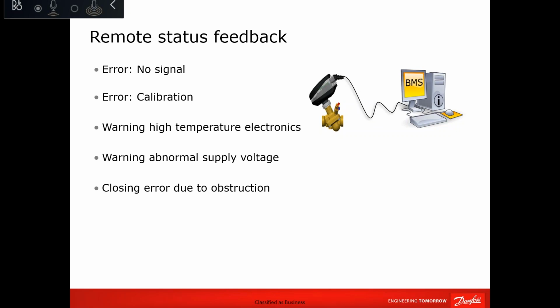Also, if the actuator is closing the valve and something is stuck inside the valve, anything can be stuck inside the valve during the flushing process, etc., you will have an alarm that you have a closing error due to obstruction. And if you are using a local analog control signal and the signal is not there, we will have an alarm on the absence of the signal. So these alarms are useful. There are still more alarms that you can see. They are more status alarms, not errors. And based on the BMS requirement, what they want to see from the actuator, it's selectable.